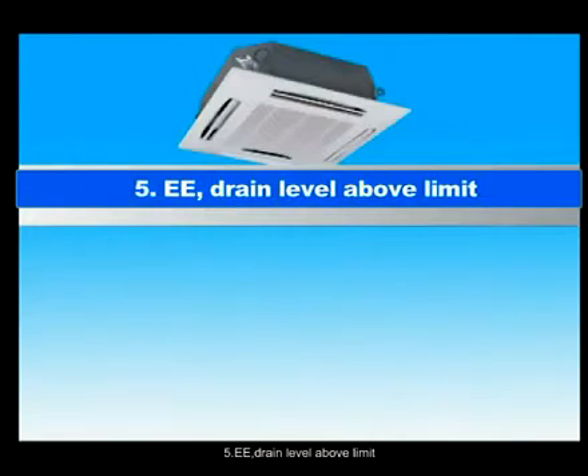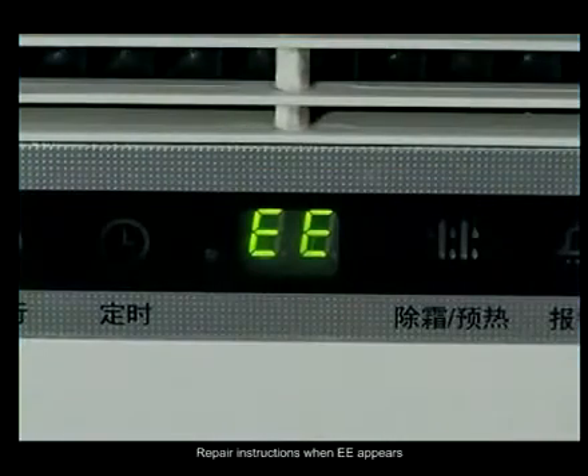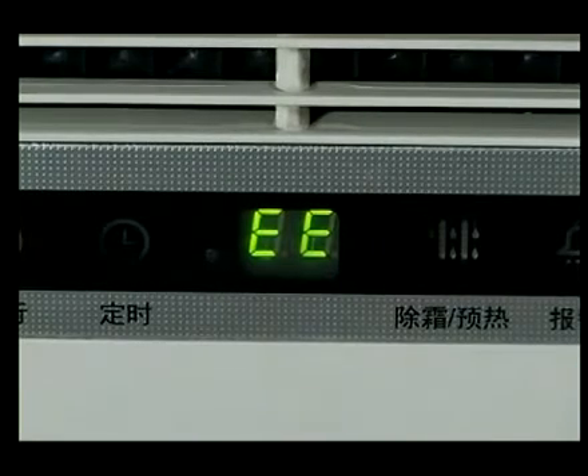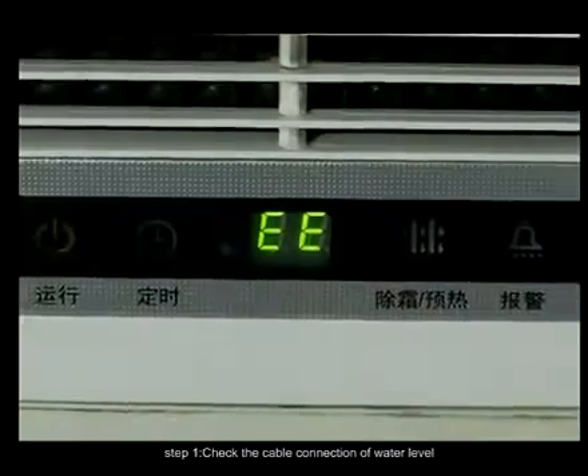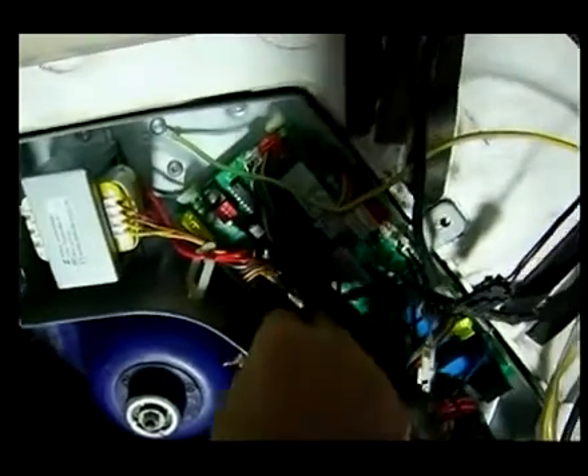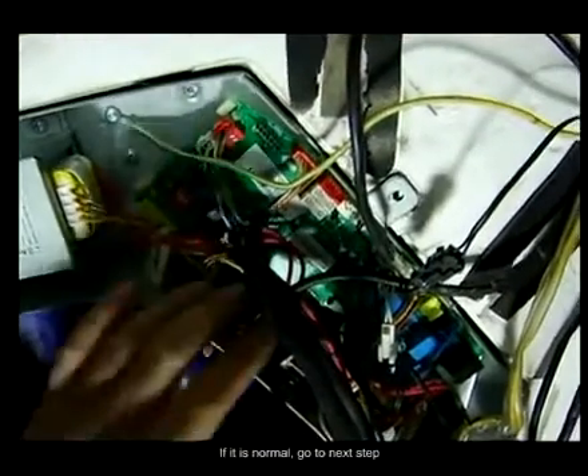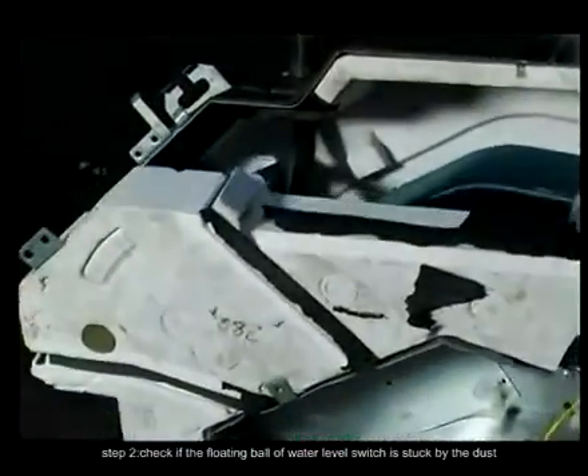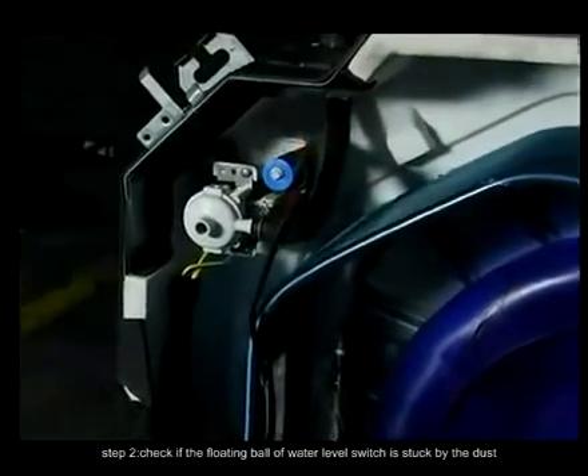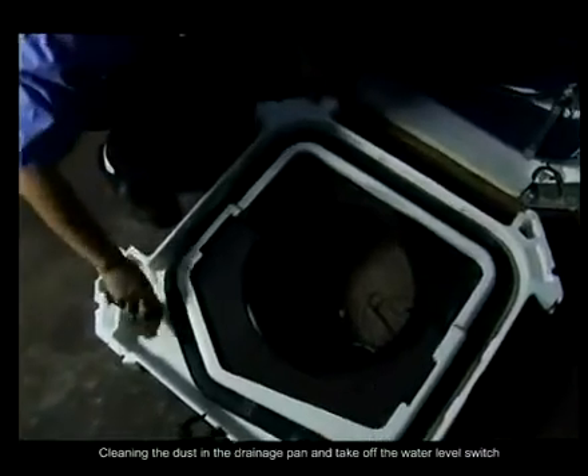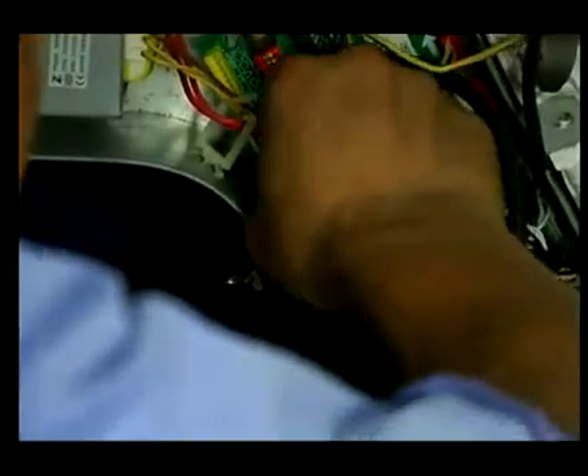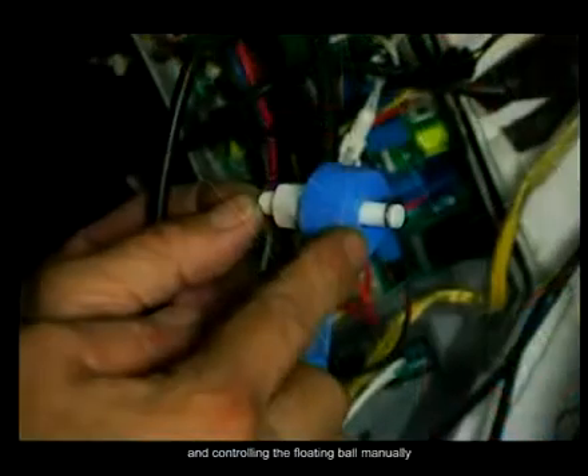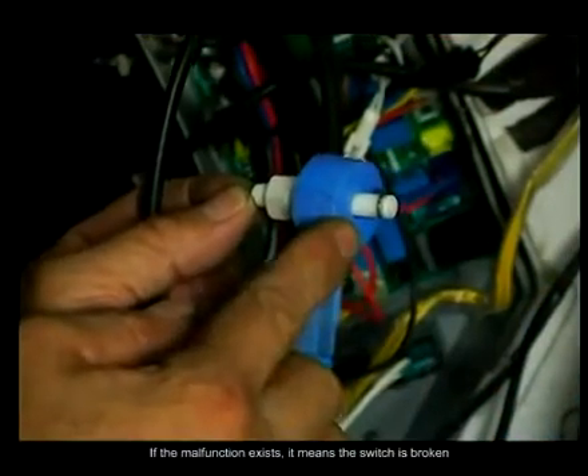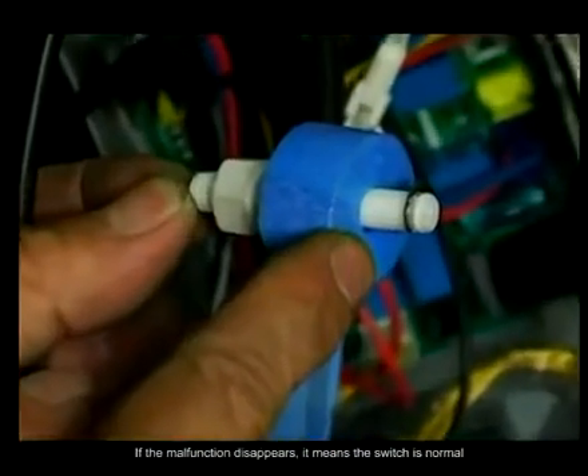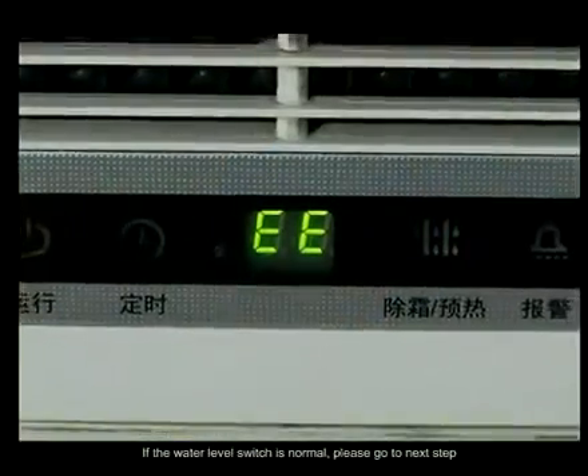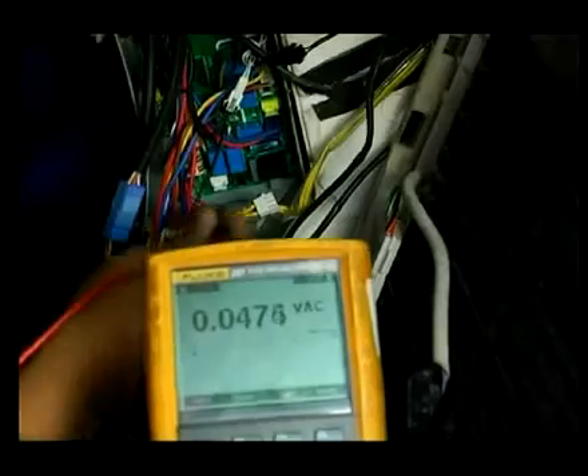5. EE, drain level above limit. Repair instructions when EE appears. Step 1. Check the cable connection of the water level switch to see if it is reliable and correct. If it is normal, go to the next step. Step 2. Check if the floating ball of the water level switch is stuck by dust. Clean the dust in the drainage pan and take off the water level switch. Connect it to the main board of another indoor unit and control the floating ball manually. If the malfunction exists, it means the switch is broken. If the malfunction disappears, it means the switch is normal. If the water level switch is normal, please go to the next step.